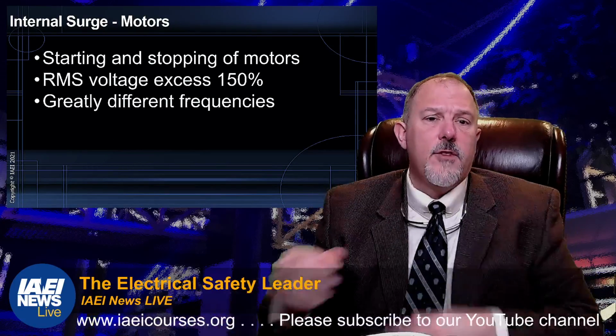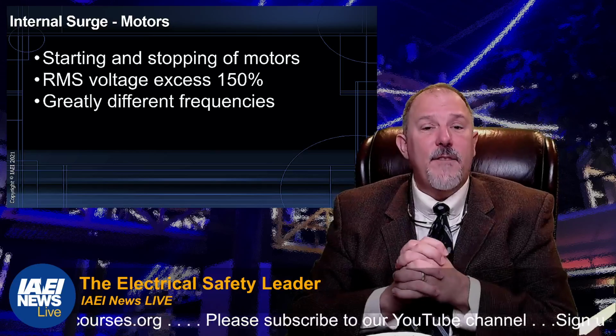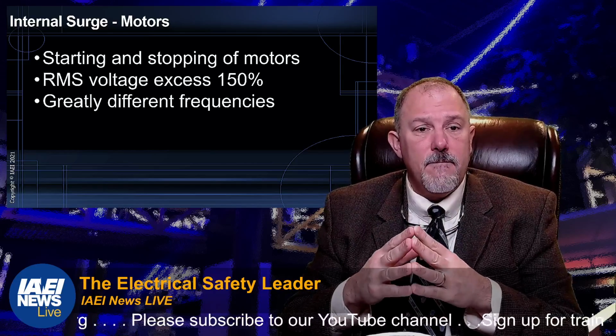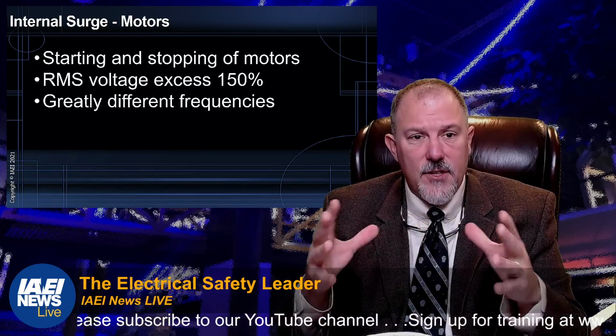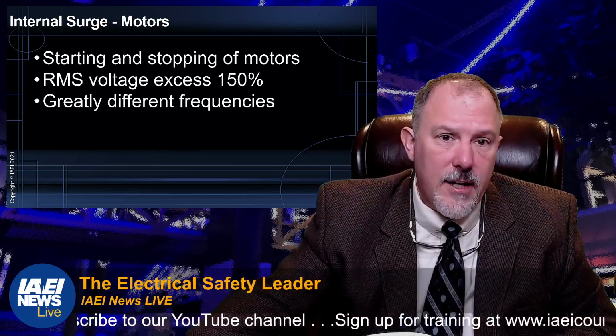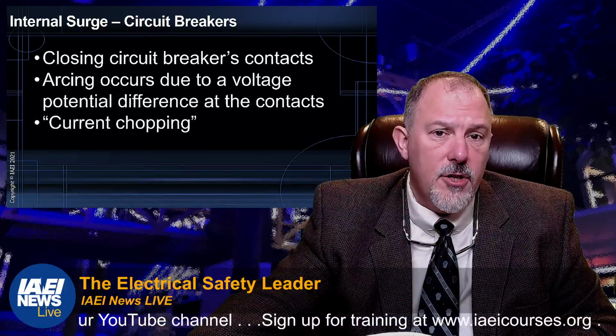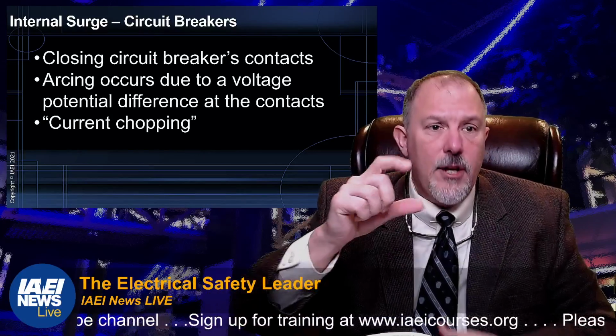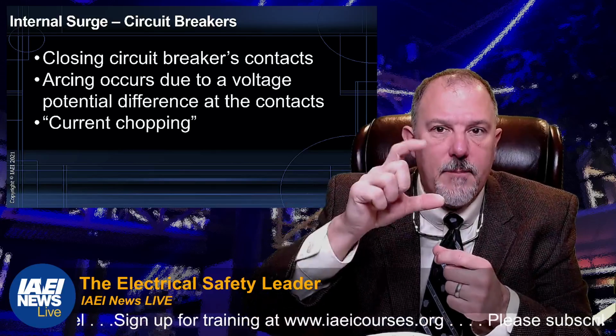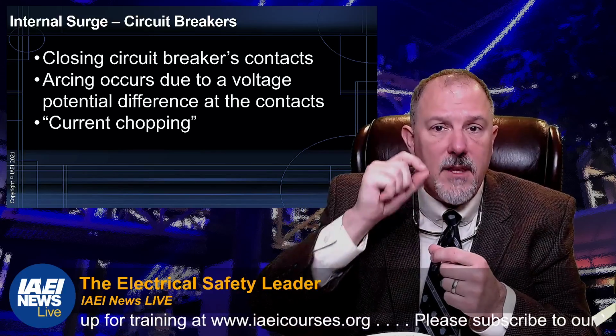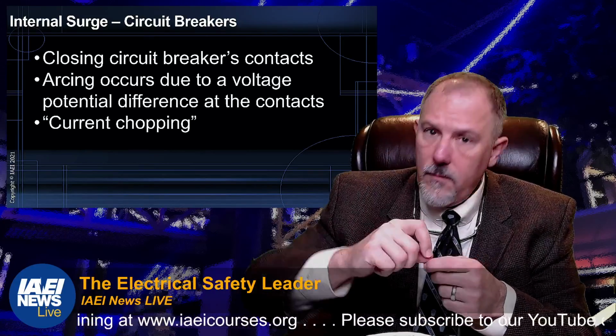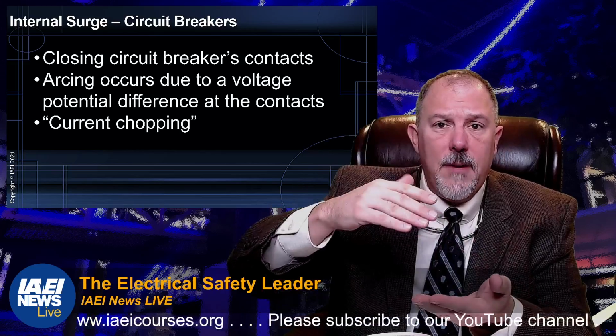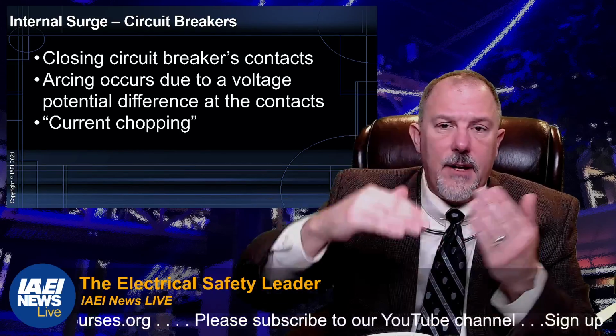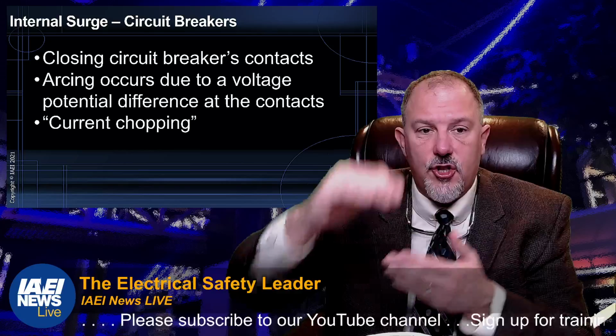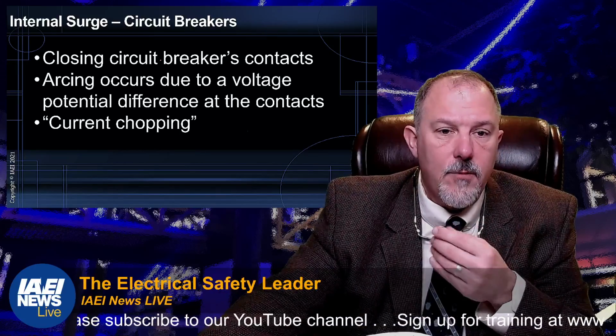The RMS voltage exceeds 150%. You can have a transient from motor starting and stopping. Closing your breakers, contacts, you're separating, you're creating an event by abruptly stopping the flow of current, drawing an arc, and you might get a change in that current fluctuation, which drives the voltage fluctuation. We call that current chopping.